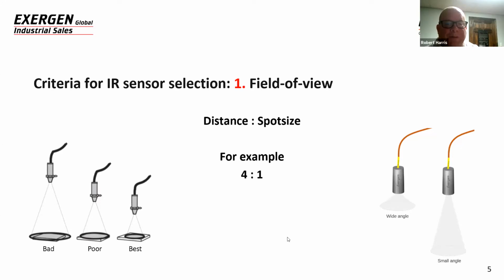Also, regarding field of view, we have sensors in different sizes that have different optics. We could go from 1 to 2 all the way up to 20 to 1 optics. The smaller size sensors that are the least expensive have the widest field of view, for example, the micro IRTC that I'm sure you're familiar with. And then we have others like the 20 to 1, an IRTC 28, for example. It's a very large sensor that has a lens and a very expensive detector, but you can measure 20 inches away and still get that 1-inch spot size. But it is also a large sensor. Next slide.